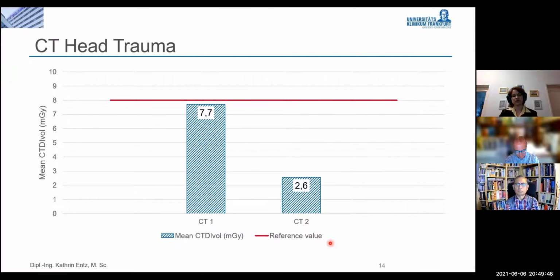And you have dose values for two different CTs, CT1 and CT2. The mean CTDIvol is displayed here, and the dose reference level here in Germany would be 8 milligray. And you can see that both our systems are well below those reference levels. So the first thing we can say is that we are good. We are below those levels.